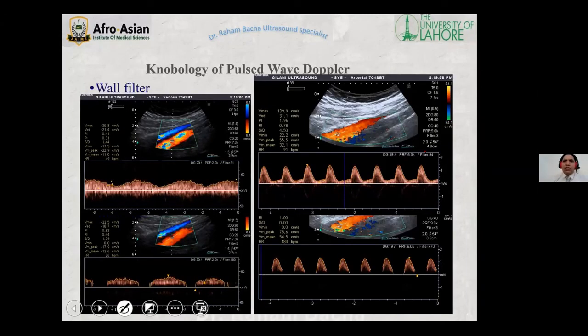By wall filter, we mean that we are going to give the machine a threshold, and the machine will eradicate or neglect all the Doppler shift below that threshold. Just for example, we have given a wall filter to this very image that is 31. So any Doppler shift below 31 hertz will be eradicated, but all the shift above 31 hertz will be depicted in the form of spectra. But here you can see the same image, the same patient, at the same time, on the same occasion. You can see now the wall filter is increased from 31 to 183, and here you can see that all the spectra near the baseline is eradicated.